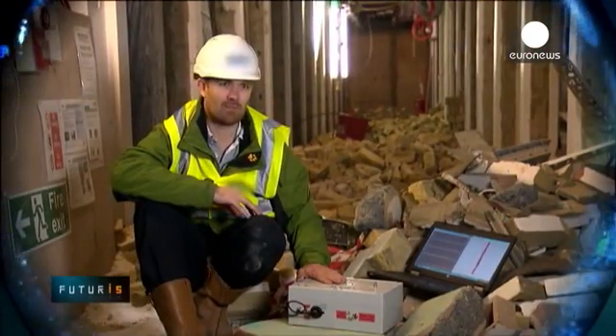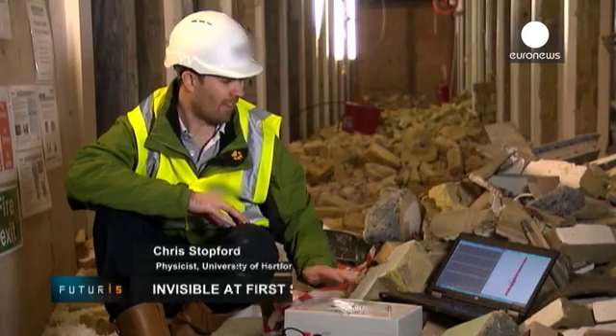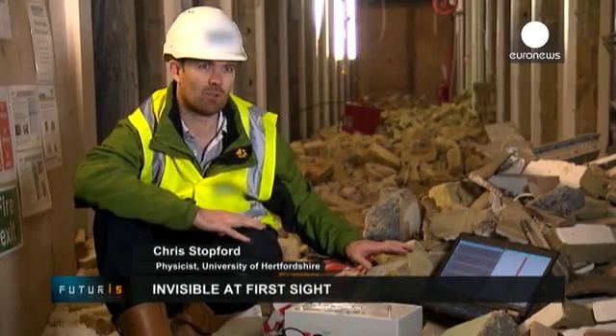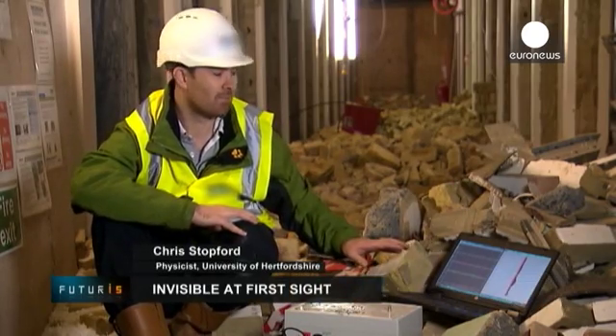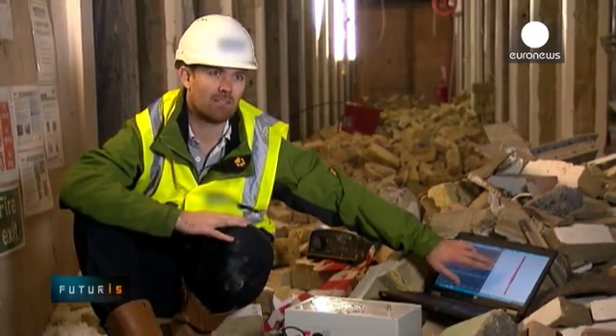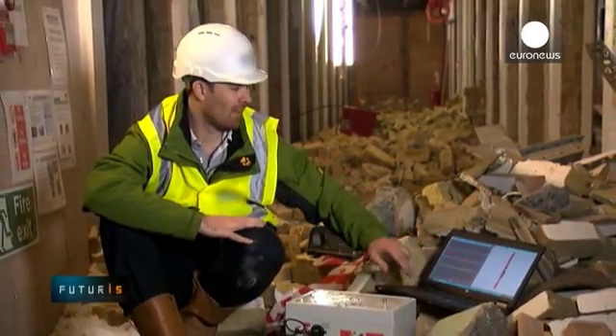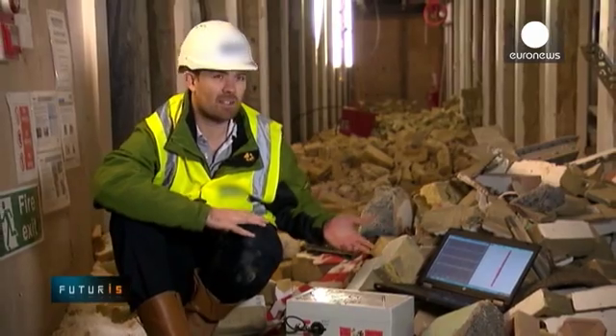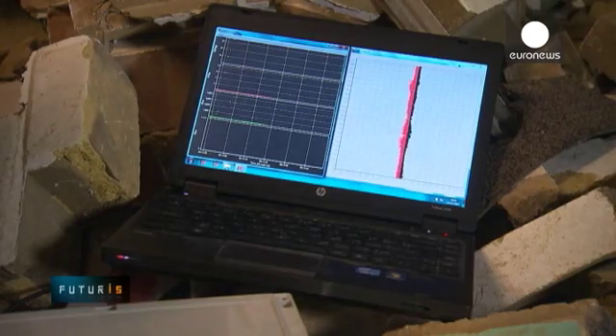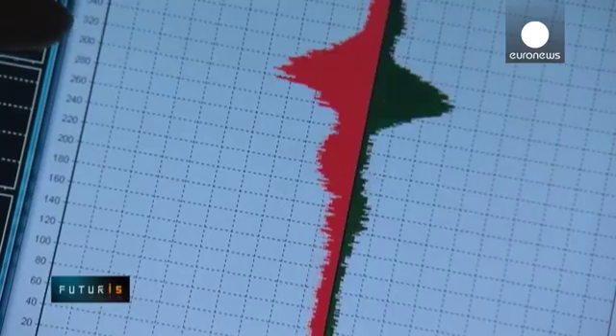This is our prototype asbestos detector, ALERT. It's currently plugged into a laptop, which does all the data recording and manipulation. This is displaying the scattering pattern from every particle that goes through the instrument. In here it's quite dusty, but it's random dust rather than being fibrous, so we're not seeing any fibres at all.